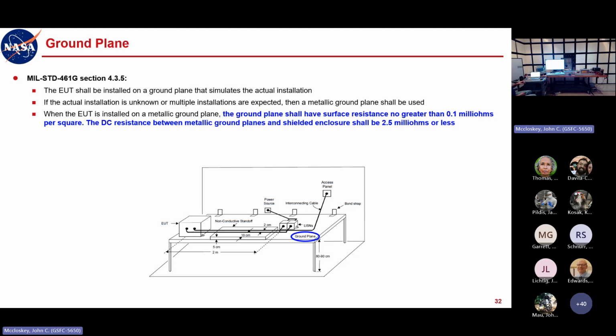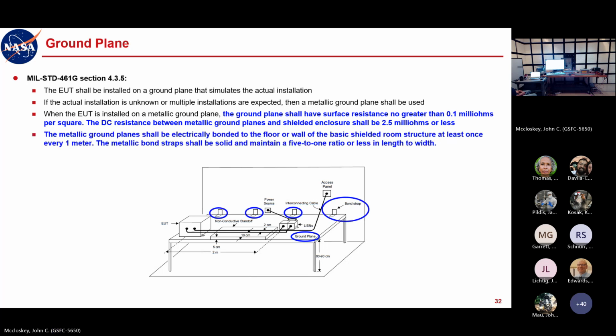I'll go through this next discussion, then show you our ground plane. One last point on this chart: the metallic ground planes shall be electrically bonded to the floor or wall of the basic shielded room and structure at least once every meter. Metallic bond straps shall be solid and maintain a 5-to-1 ratio or less in length to width. I didn't specifically point this out, but that's a class R bond for, I believe, NASA standard 4003.